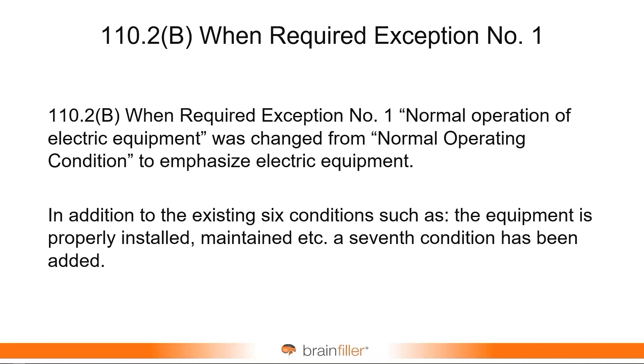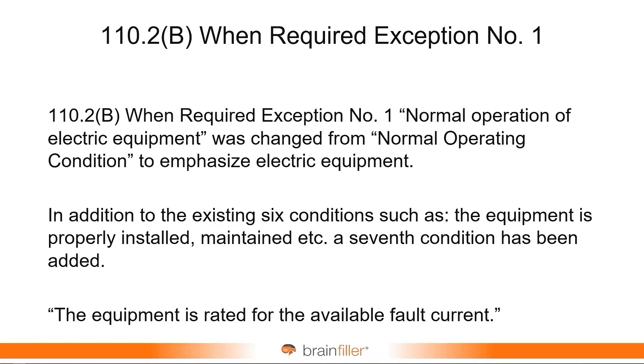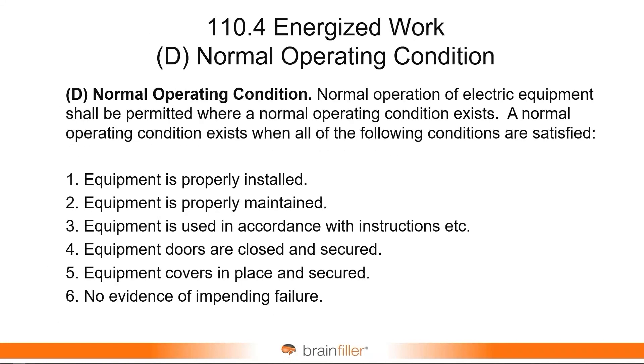This is where you find the six conditions that define the normal operation of electric equipment. There's been a seventh condition that's been added: the equipment is rated for the available fault current. Previously in 2021, it was referred to as normal operating condition, and we had six conditions: the equipment is properly installed, properly maintained, used in accordance with the instructions, the doors are closed and secured, the covers are all in place and secured, and there's no evidence of impending failure.